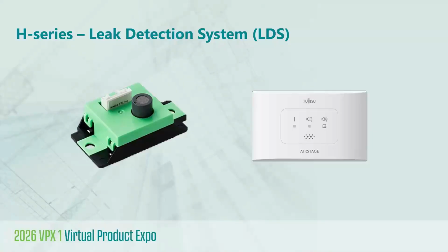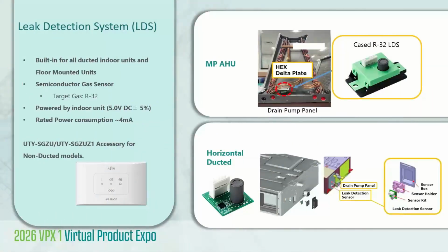Now let's dive into the leak detection system accessories. The LDS is pretty much built in all the ducted indoor units as well as our floor-mounted units. This LDS sensor is designed to detect the R32 refrigerant leak. The sensor is powered by the IDU itself, and the power consumption is so low, around 4 milliampere, that even if the indoor unit is powered off, the sensor continues to work and detect refrigerant leak. The accessory you see below, the UTY-SGZU and the Z1 version of it, are compatible with our non-ducted models.